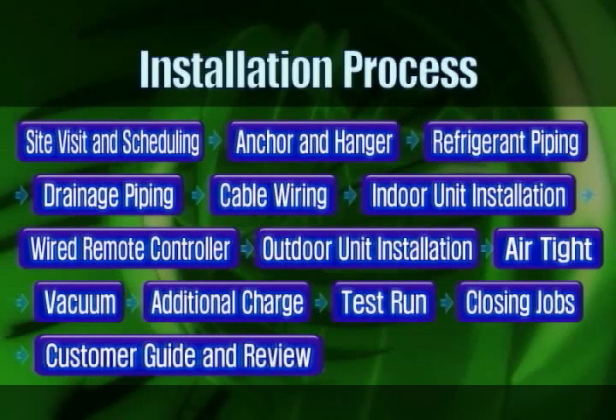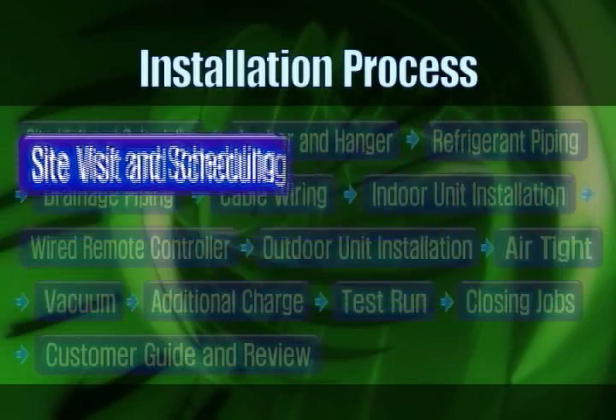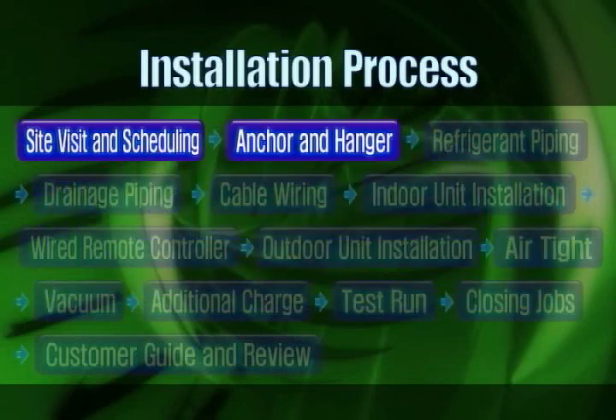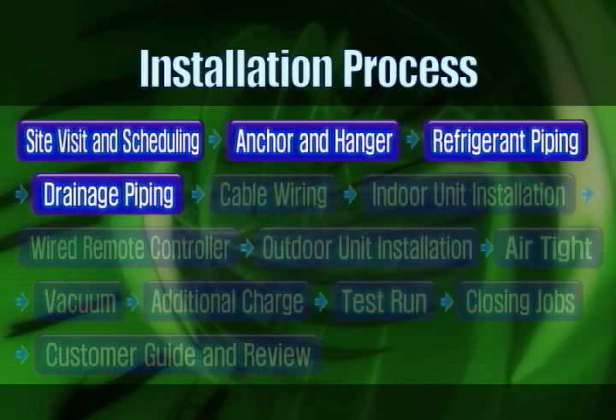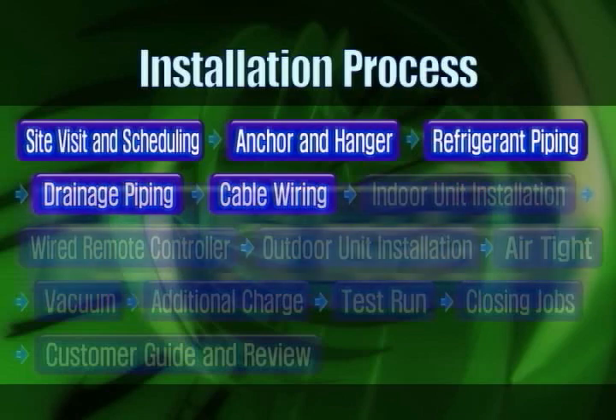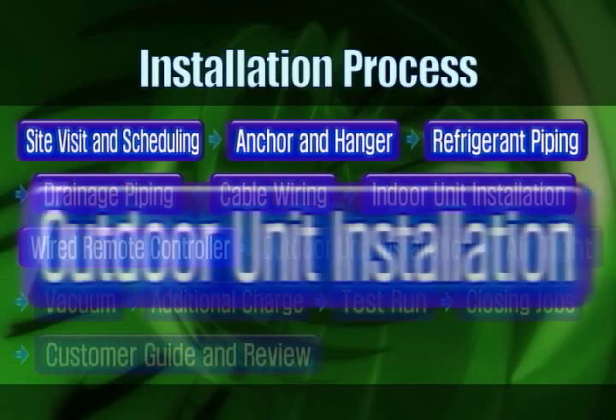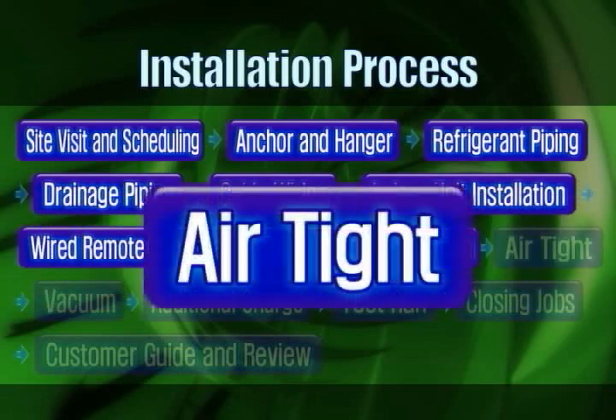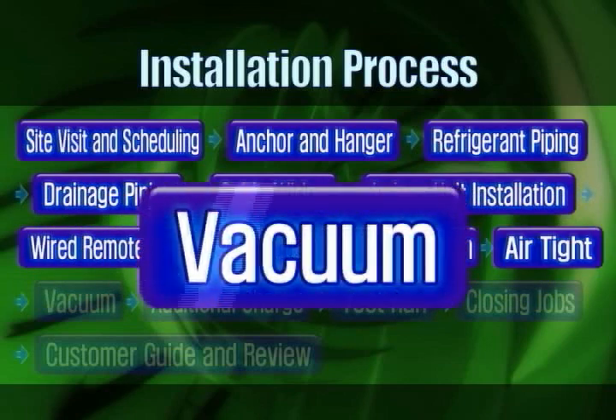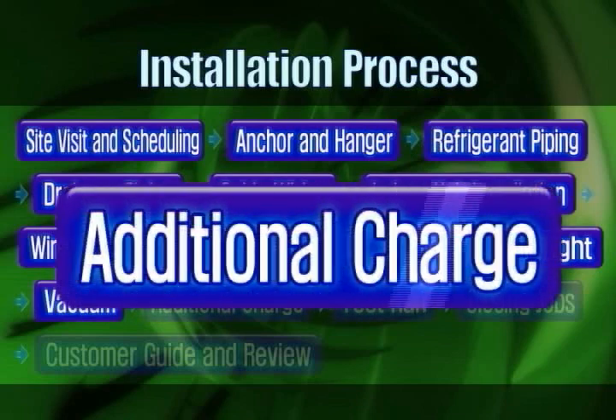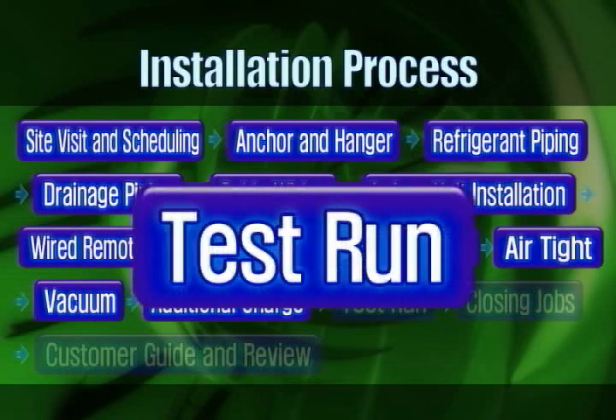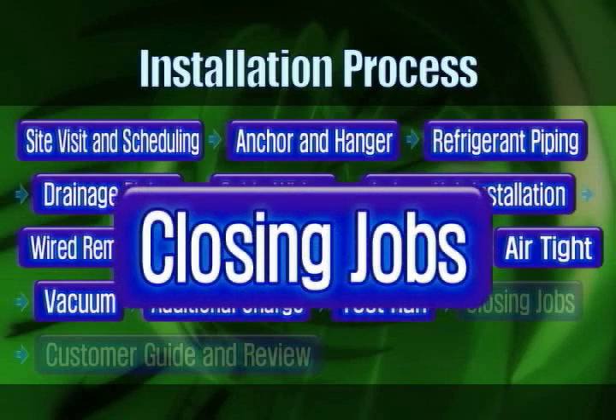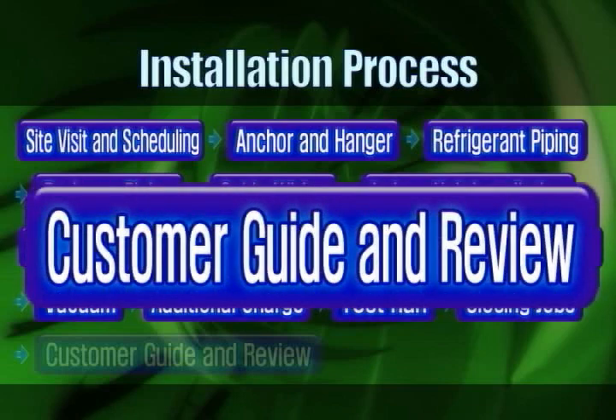Installation sequence for the Multi-V Plus air conditioner is as follows: site visit and scheduling, anchor and hanger, refrigerant piping, drainage piping, cable wiring, indoor unit installation, wired remote controller, outdoor unit installation, airtight, vacuum, additional charge, test run, closing jobs, customer guide and review.